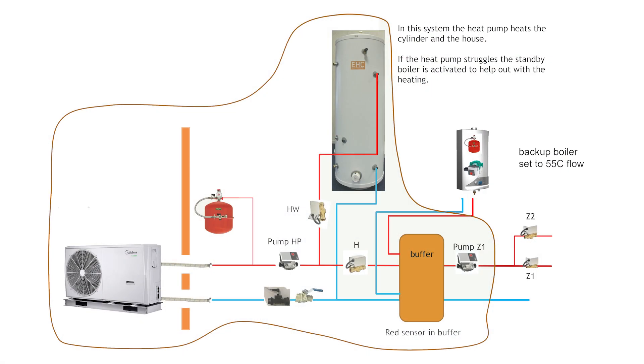When the weather is milder — in autumn, springtime, and early or late winter when it's not too cold — the heat pump is going to heat the house simply on its own, with the boiler idle. But when you get those really cold days, down towards around two or three degrees centigrade or colder, the heat pump turns off and the boiler automatically fires, heating the same radiators and hot water cylinder just as before.